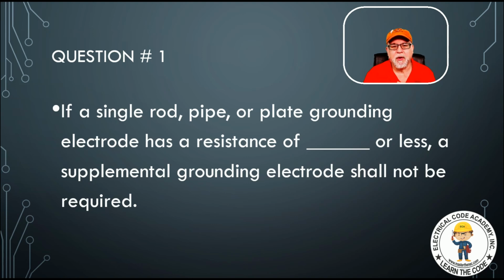So back in the day, we used to put in one ground rod. And if we couldn't show it was a specific ohms value, then we would put in a second one. So in the 2020 code, and it's been like this for two cycles or more, you have to put in two, or you have to put in a single rod and some other electrode to supplement it, unless you can show that it was a certain ohms value or less. And if you did, then you could just keep the one, and that's all you would need.